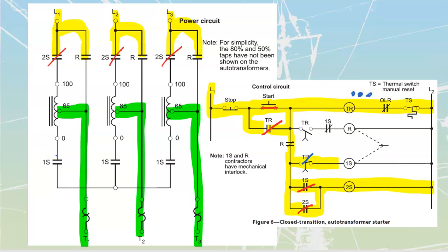There is still going to be a path for current through to my load. Because right now, with 1S gone, we can just carry current directly through this top section of the winding over here, which is going to be in series with the motor. But we're able to carry that through out to the motor. So we see that this one here has opened up. As that one opened up, it depowered the 1S, which is going to depower that set of contacts there. Sorry, 2S is still there. That line just disappeared because it was attached.